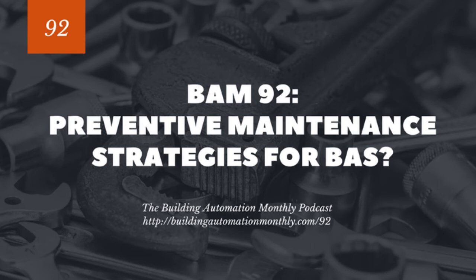Is it reasonable to think that an 85-degree discharge air temp on a unit that uses steam heat or electric heat would only ever be 85? That may not be reasonable, you may have a discharge air temp much higher than that. Or you have a unit with no heat, and you're setting a discharge air temp alarm of 85.